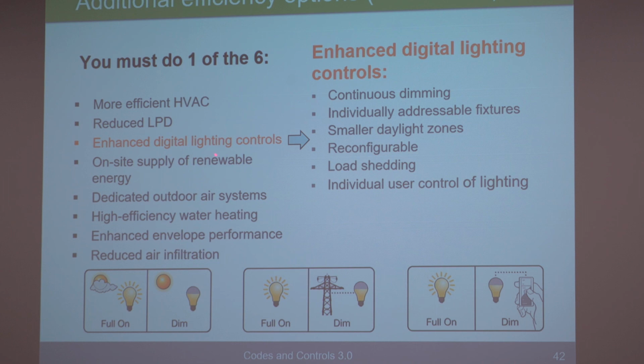Or they added what they call enhanced digital lighting controls. And what is that? That's basically a lighting system that does this, provides continuous dimming. The fixtures are individually addressable. You can select your specific daylight zones. They're reconfigurable, meaning you can easily, without rewiring, change what controls are controlling a light fixture. So these fixtures are controlled by this sensor, and then later, if the space changes, you can change it to being controlled by another sensor, for example. Load shedding lighting load, especially for demand response purposes, and giving users personal control of the lighting in their individual workspace. So if you have a system that does that, that'll comply with that optional energy efficiency provision.